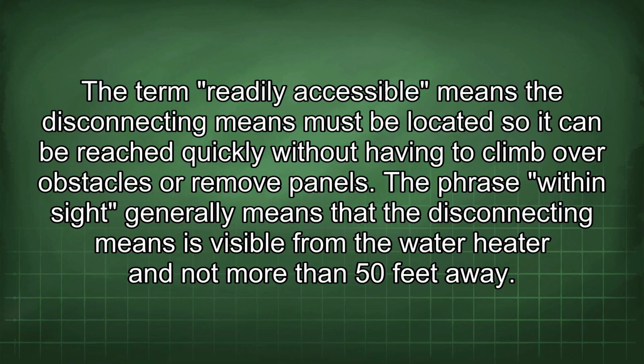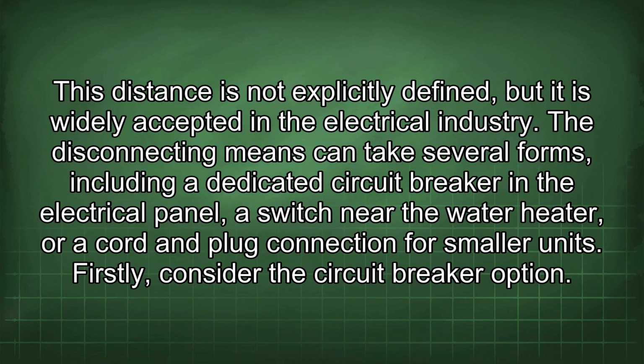The phrase within sight generally means that the disconnecting means is visible from the water heater and not more than 50 feet away. This distance is not explicitly defined, but it is widely accepted in the electrical industry. The disconnecting means can take several forms, including a dedicated circuit breaker in the electrical panel, a switch near the water heater, or a cord and plug connection for smaller units.